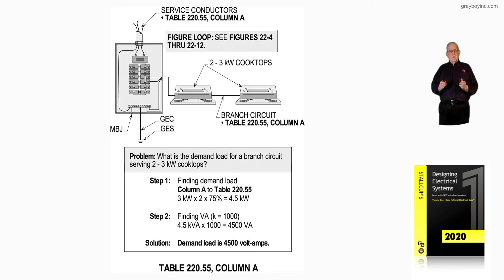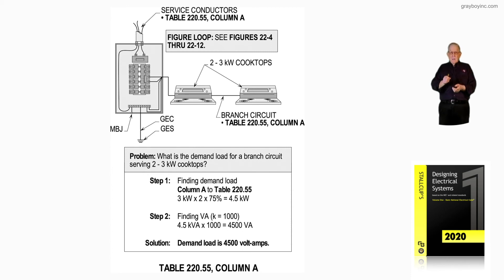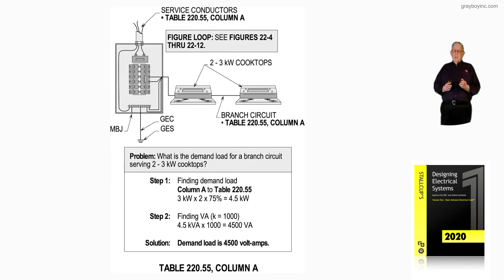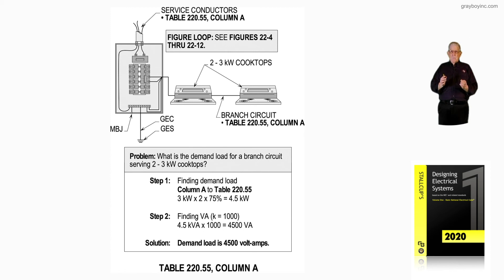The concept is: I turn the heat up, heat the element up, bring the water or whatever I'm cooking to temperature, then turn it back and slowly cook it — otherwise I'd burn it. So I never use the full load, or I'd burn my food. In Step 2, I take 4.5KVA times 1,000. When I multiply by 1,000, I get rid of the K and do the math — now it's VA.